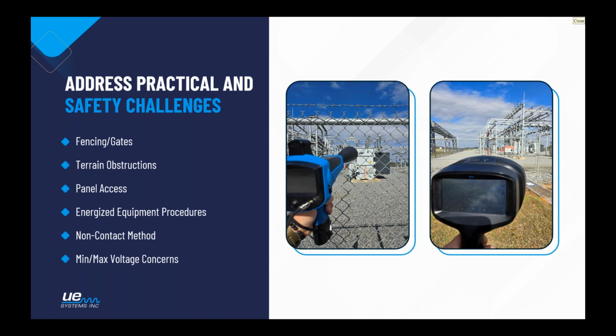And then with that being said, with the ultrasound range, one of our concerns is always, is the equipment energized or not? We're not necessarily concerned with what the voltage of it is, other than for reporting. We can hear electrical events happening regardless of the minimum or maximum threshold of that piece of equipment. The only time we really need to know that is for the actual reporting side of it. So, it gives us a lot of assets that we can go out and inspect on a daily basis.